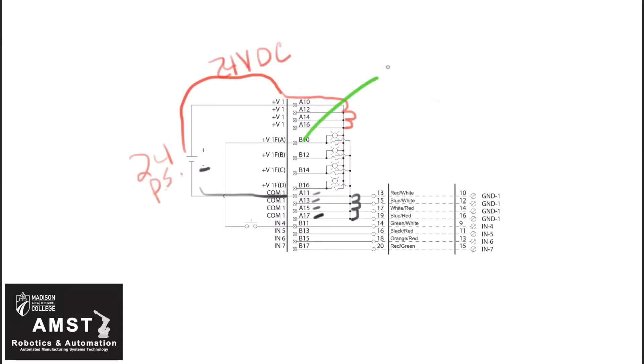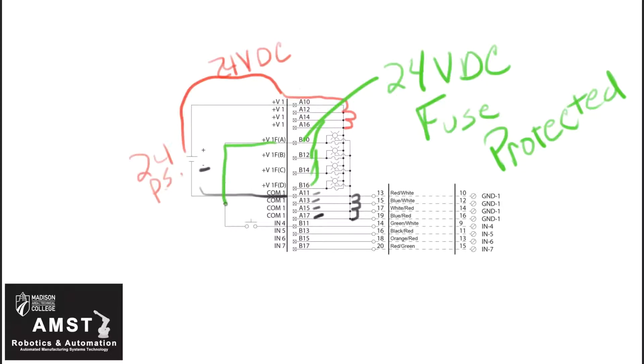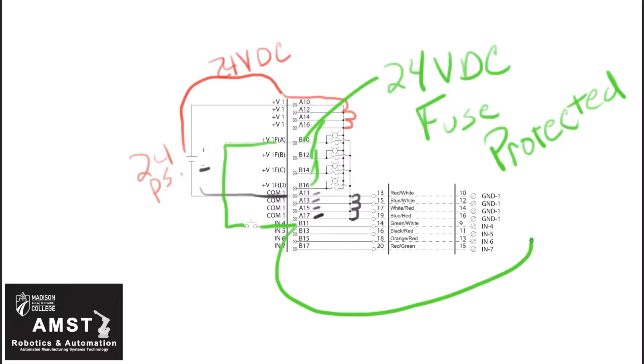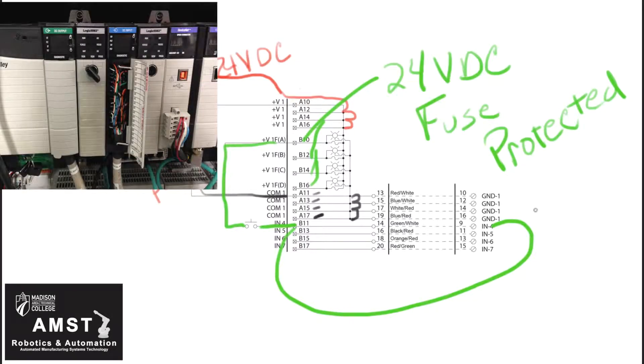Let's talk about terminals B10 through 16. They're actually fuse protected, and they'll feed the supply to your field device. In this case, it's a simple switch. So B10 through 16 are fuse protected, come into your switch, and once the switch is made, it'll come to B11, and that feeds input 4 on your I/O module up on your PLC, which is pre-wired and connected to your IFM.